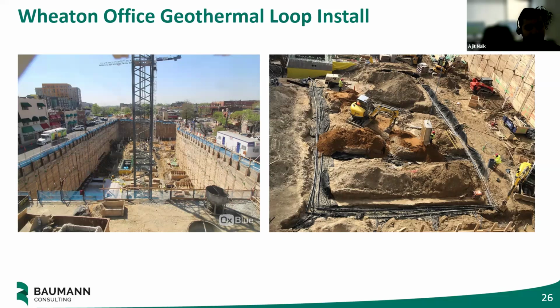All that to say, if you're going to put vertical boreholes underneath a building like this, you better be damn sure they're not going to leak and that everything is going to work, because there is no chance, no opportunity to fix it. I believe the detail on top of the bore field shows 18 inches of dirt, 36 inches of gravel, and then a net of 36 inches of concrete over these boreholes. So literally, we're not getting at them if something is leaking. It was super important that we made sure their design process was adequately done, that all the checks, tests, and inspections necessary in the construction phase were included in the construction documents and contract documents, and that it was really built right.